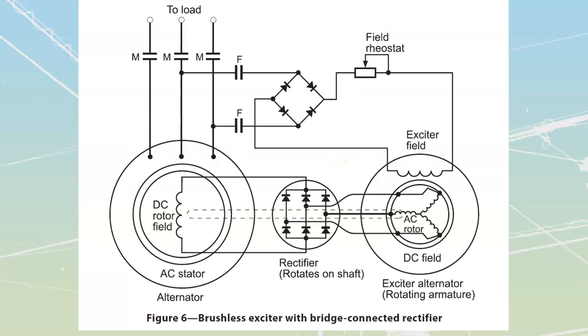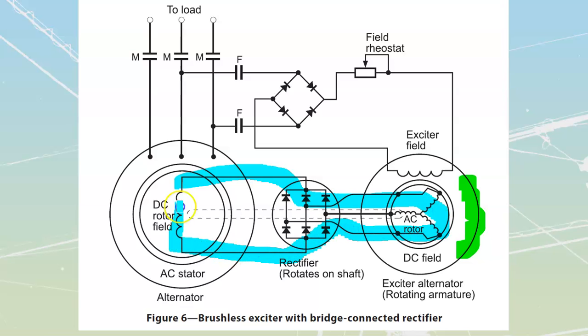There's a better method called the brushless exciter. The brushless exciter is actually pretty cool when you take a look at it. We're going to start this out with a little bit of residual magnetism inside my exciter alternator. This has got a whole pile of stuff that is physically bonded onto the main shaft. None of these components inside here ever leave that main shaft.